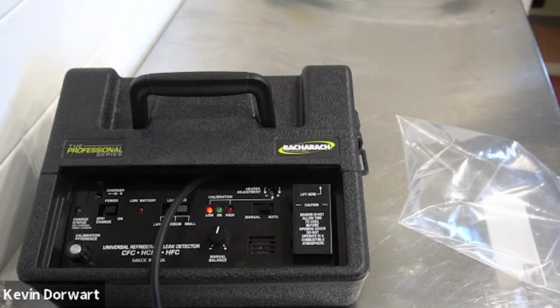If I stop moving the probe in auto mode, the unit will zero out and return to about a one click per second increment. So it is imperative to continuously sweep the probe in auto mode while searching for leaks.